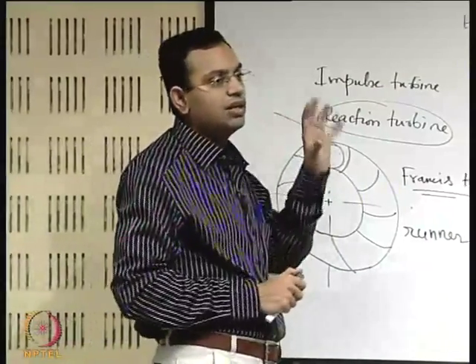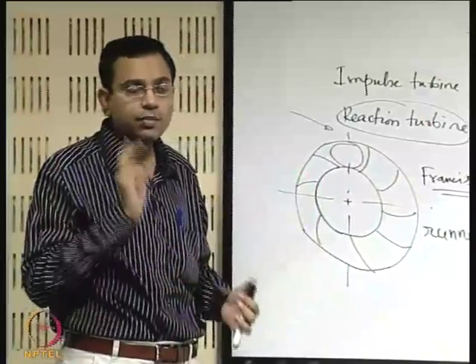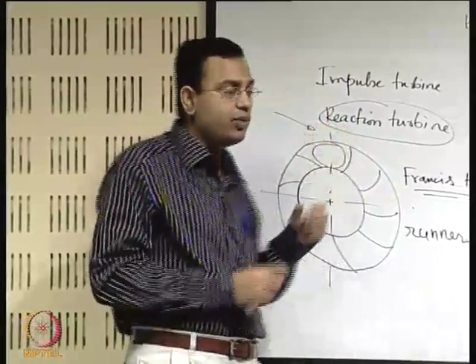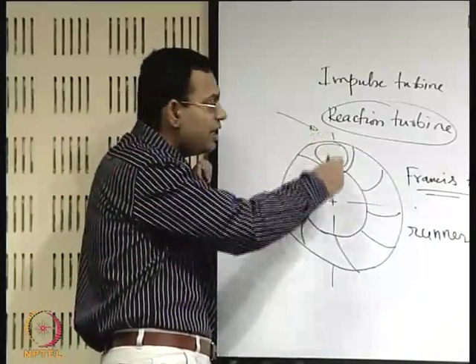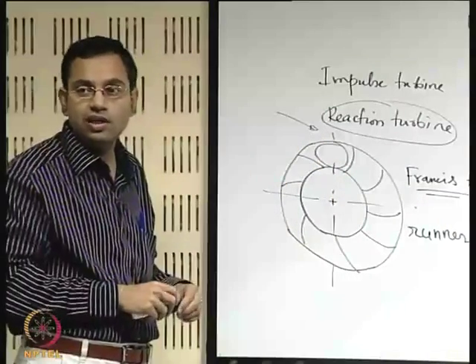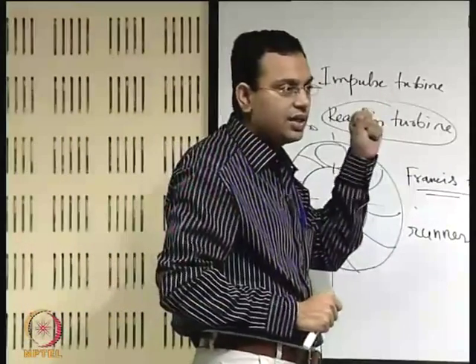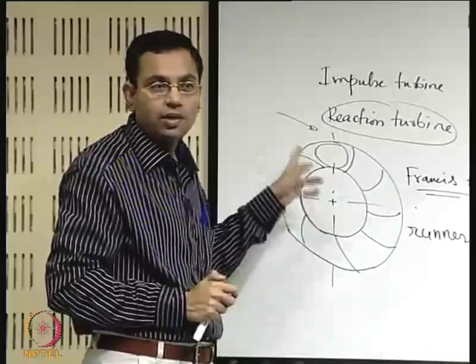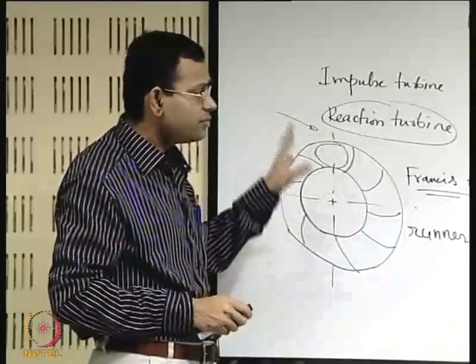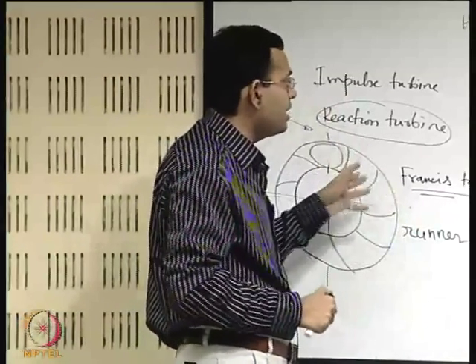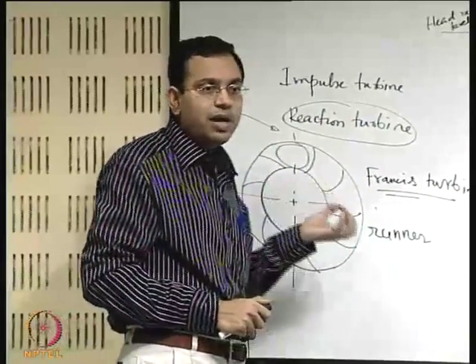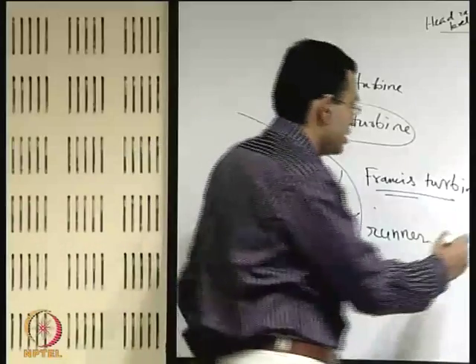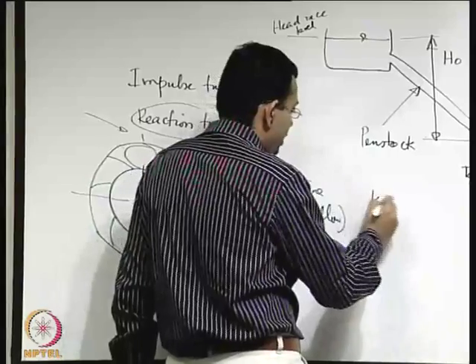The name 'reaction' is somewhat of a misnomer: there cannot be a 100% reaction turbine — there must be at least some impulse of the jet to begin with. There are many types of reaction turbines: the Francis turbine is a radial flow reaction turbine, and there are also axial flow reaction turbines. An example of the latter is the Kaplan turbine.